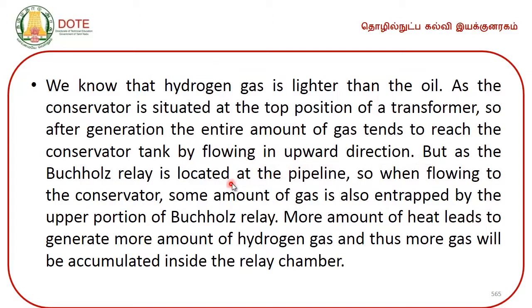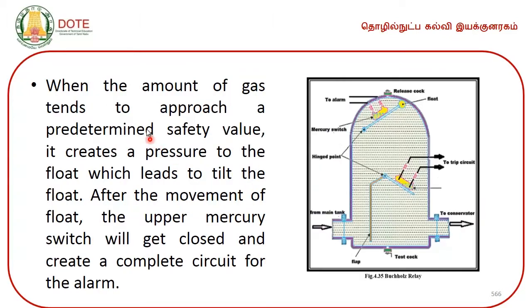But as the Buchholz relay is located at the pipeline, when flowing to the conservator, some amount of gas is also entrapped by the upper portion of Buchholz relay. More amount of heat leads to generate more amount of hydrogen gas, and thus more gas will be accumulated inside the relay chamber. When the amount of gas tends to approach a predetermined safety value, it creates a pressure on the float which leads to tilt the float. After the movement of the float, the upper mercury switch will get closed and create a complete circuit for the alarm. So, this is the schematic diagram of Buchholz relay.